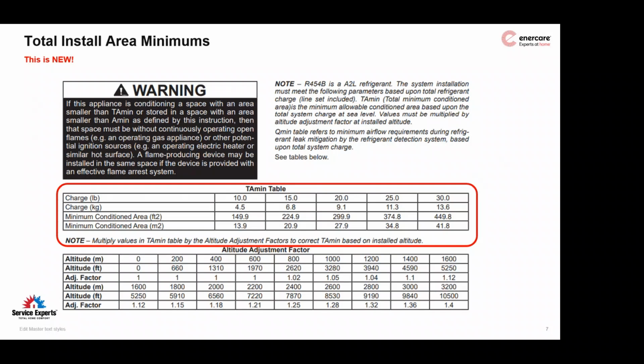One thing that's new for all of us. Speaking of installation planning, the indoor space where this A2L AC or heat pump is going to be installed now requires a little more careful consideration based on the total refrigerant charge, as you can see across that highlighted TA min table, a minimum conditioned space requirement. Now, it doesn't look too crazy. That warning in the left corner kind of explains it. This is page 4, by the way. So the warnings do continue.